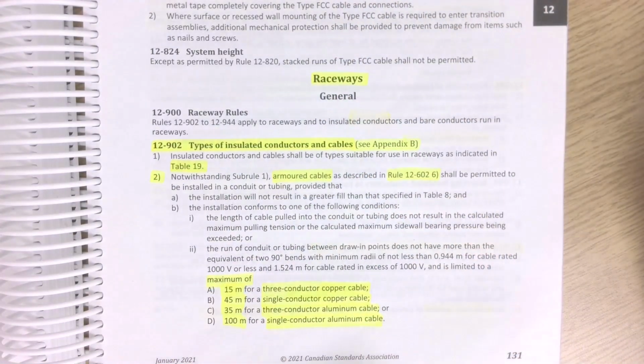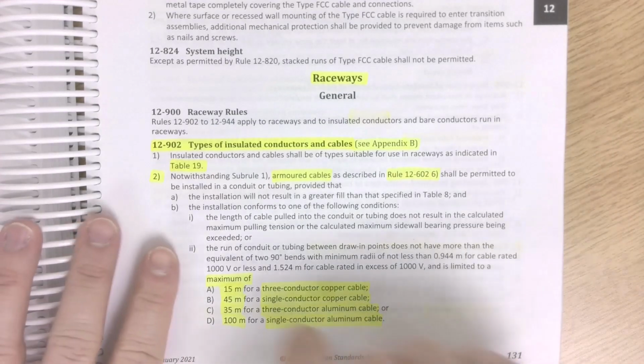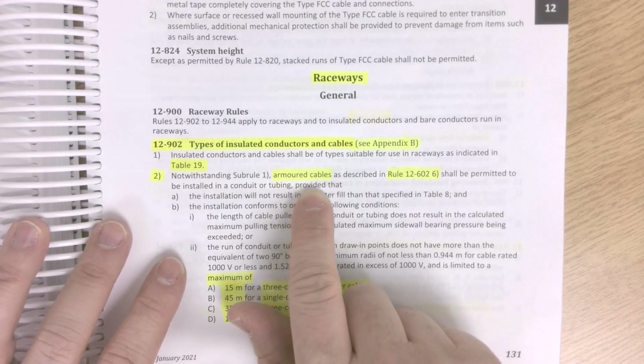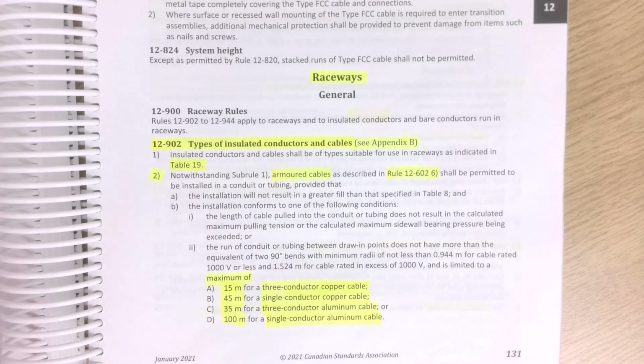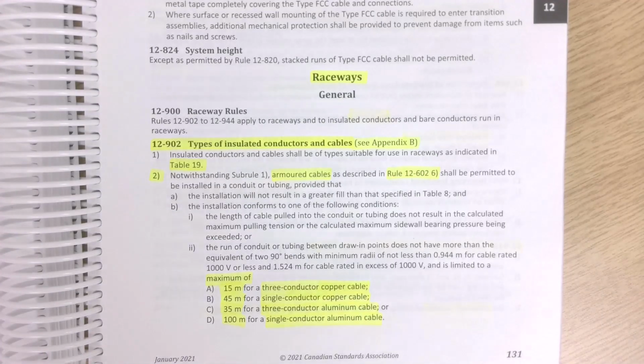In general, we're going to pull in individual conductors, or maybe some control cables or data cables, but we're not usually going to pull armored cable into a raceway, or NMD, or non-metallic sheathed cable, into a raceway. We might at times to give them some extra protection, because a raceway has more structural integrity, let's say, than AC90 or NMD90.